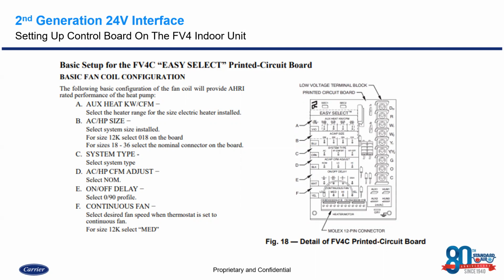This tap will determine what that fan speed after a set point is going to do. Now you see the only rule on here for CFM is going to be for the 12,000 models. We need to make sure that we select medium continuous fan speed for those models. Everything larger than a 12,000 BTU can select between a low, medium, or high tap. Okay, and again, that's for after the set point is reached. The fan will continuously run, so we need to make sure that our customers understand that the fan is not going to shut off. We're going to continuously cycle that air.